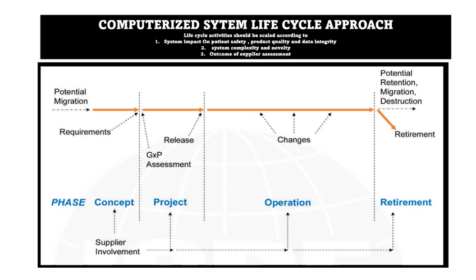The life cycle approach for computerized systems includes four major phases. The first is the concept phase, where you evaluate the requirements of the computerized system based on business needs. The second is the project phase, where we validate the computerized system and after validation the system is released for routine use.